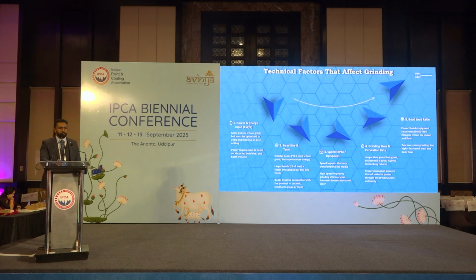Now technical factors that affect grinding. First one is power. More power, finer grind. But again, if you increase the power a little bit more, there are heating issues generated in the machine. Bead size, typically the lower the bead size, the finer the grind, but people go for 1 to 2 mm beads. Tip speed is the speed of impact, the force that is transferred from the beads to the particles. Grinding time is the amount of time it takes for the whole particles to be ground in the machine. And bead load ratio is typically from 60 to 85%. With a lower bead load ratio, you won't have proper grind, and with a higher bead load ratio, the material doesn't move properly in the machine.